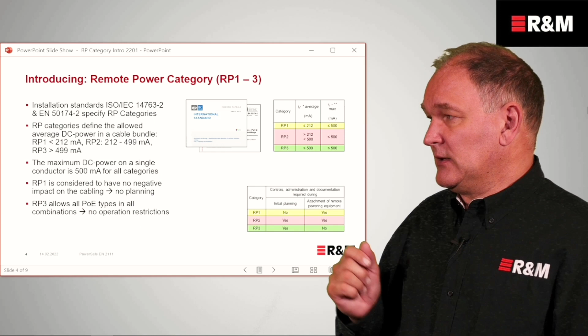On the other hand, with an RP3, you have to make the planning such a way that your installation is allowing to attach type 4 PoE on every cable. But on the other hand, during operation of the installation, you don't have to do anything anymore because it's already planned for the worst case.